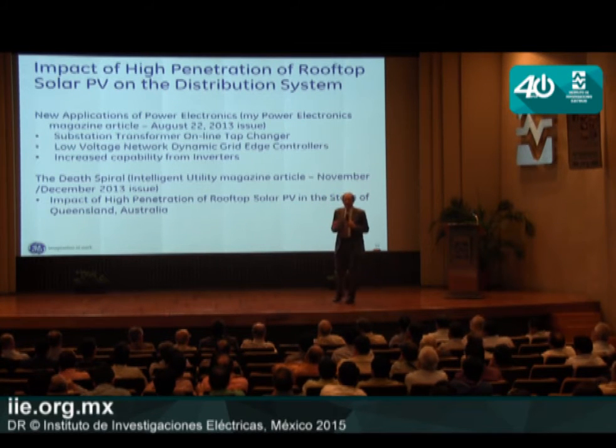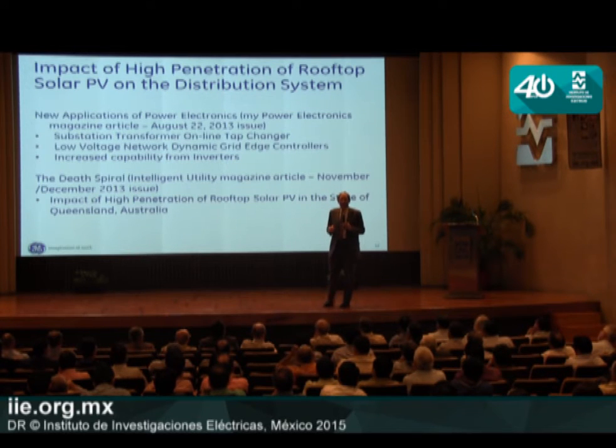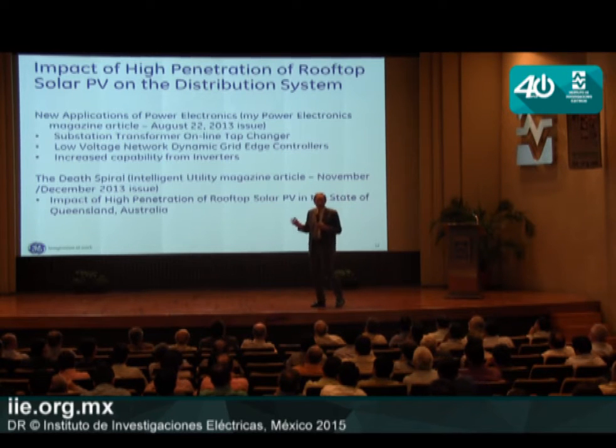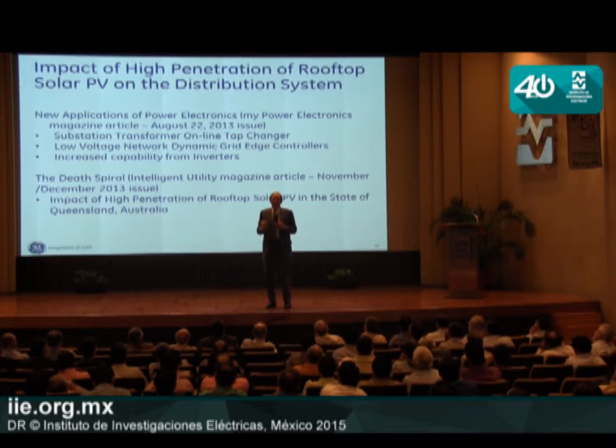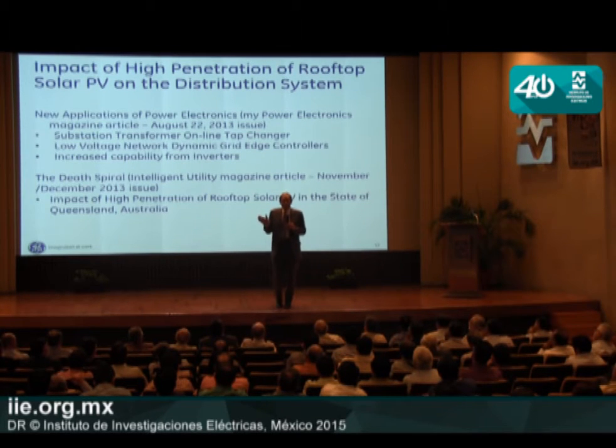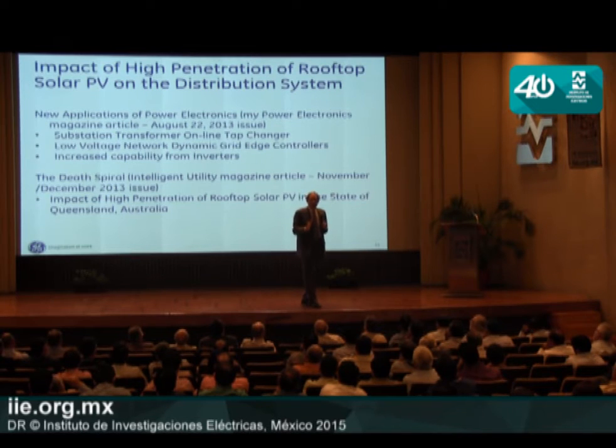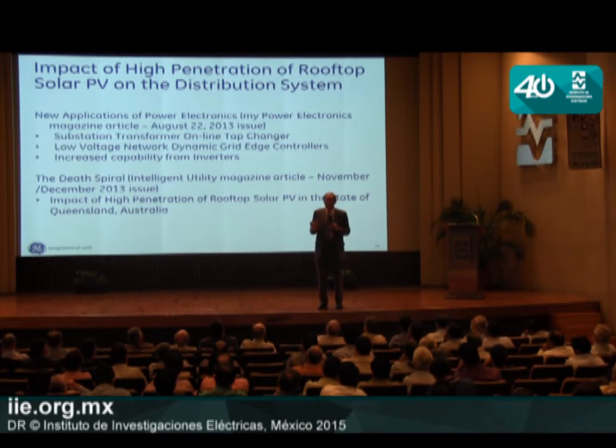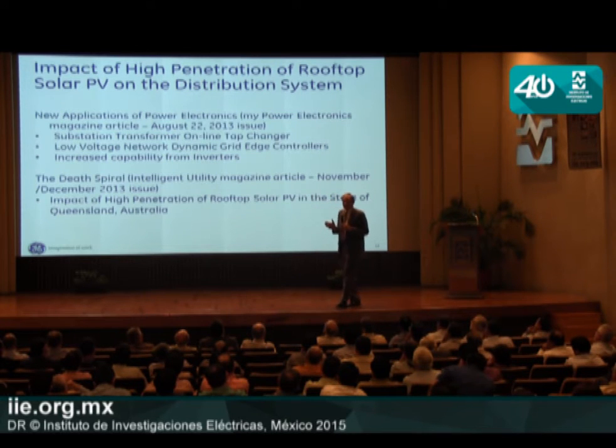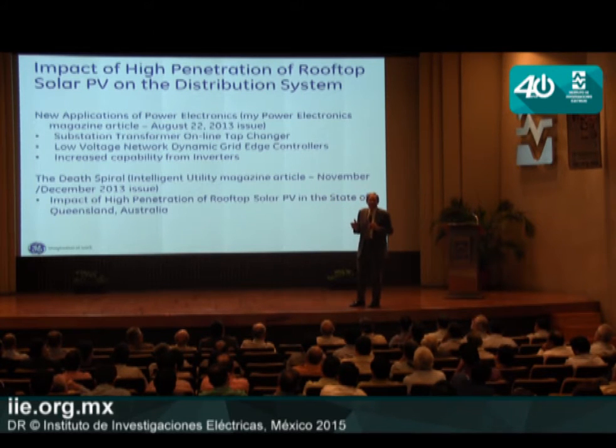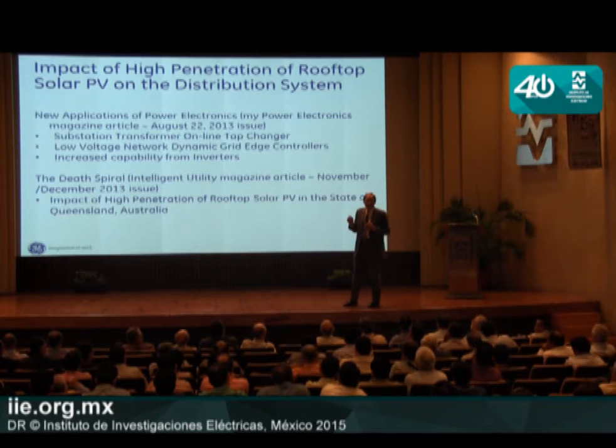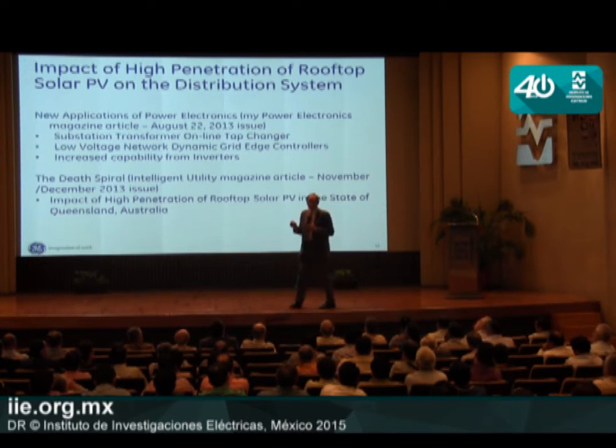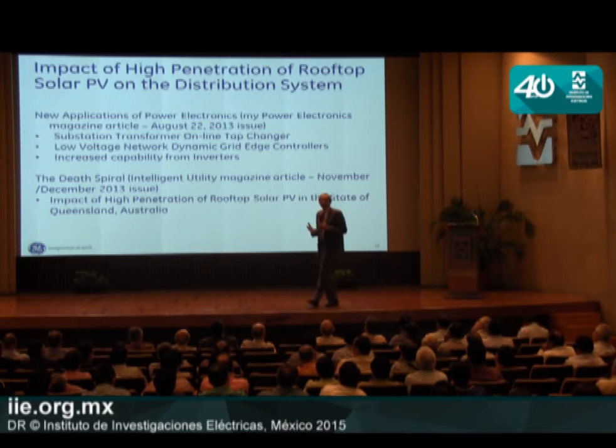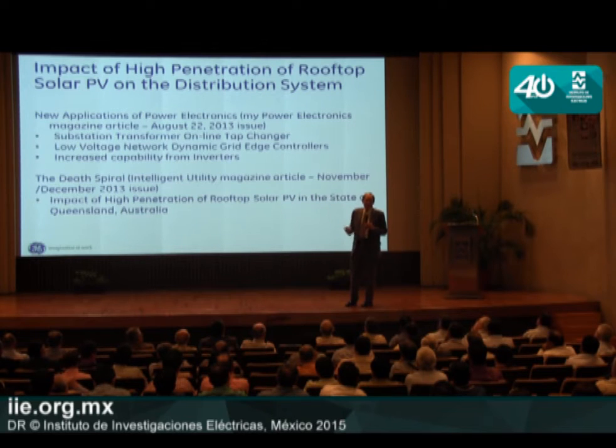Third, we need more capability from inverters, what we call smart inverters. We have a list of new functionality we'd like to see from inverters, plus additional capability to externally control the inverter. The inverter is a very good source of reactive power compensation, a very good VAR resource. We amended IEEE standard 1547, the standard on rules to integrate renewables to the grid, a year ago so that we can now use inverters for VAR compensation. So this is the smart inverter.